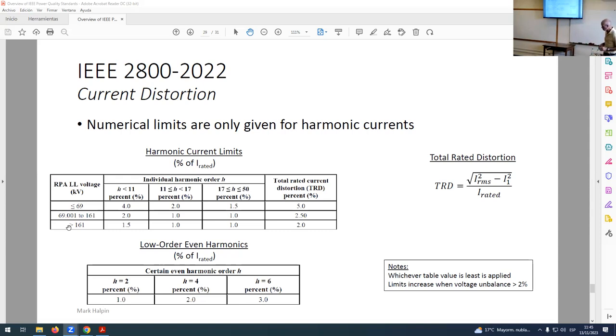Well, okay, but how do the current limits change? The way it's written, for every 1% increase above 2%, okay? So 2% unbalanced or below, this applies as is. But if this goes from 2% to 3%, every 1% increase in unbalance, these numbers double. Okay? This goes up 1%, those go up 100%. This goes up 2%, those go up 200%.